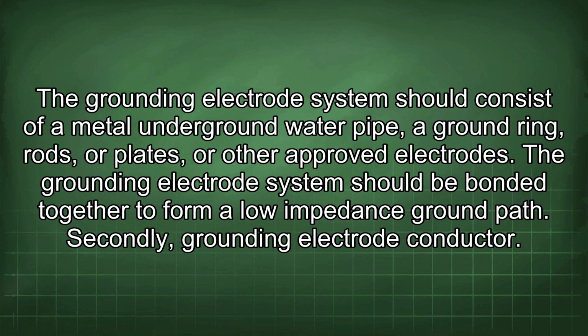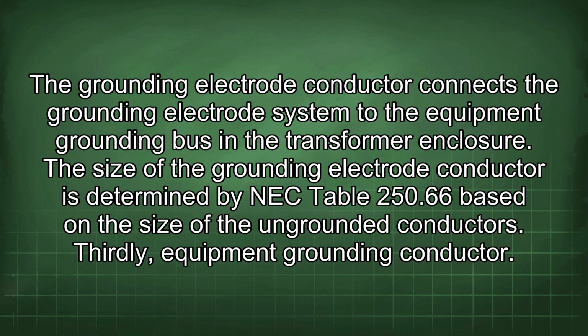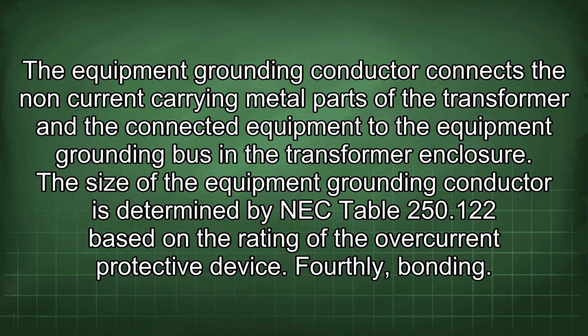Secondly, grounding electrode conductor. The grounding electrode conductor connects the grounding electrode system to the equipment grounding bus in the transformer enclosure. The size of the grounding electrode conductor is determined by NEC Table 250.66 based on the size of the ungrounded conductors. Thirdly, equipment grounding conductor. The equipment grounding conductor connects the non-current carrying metal parts of the transformer and the connected equipment to the equipment grounding bus in the transformer enclosure. The size of the equipment grounding conductor is determined by NEC Table 250.122 based on the rating of the overcurrent protective device.